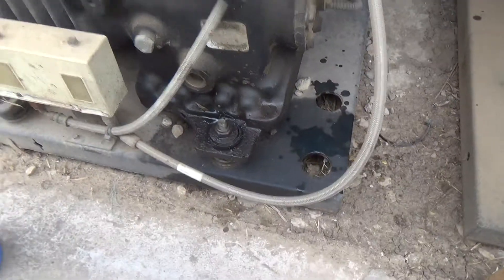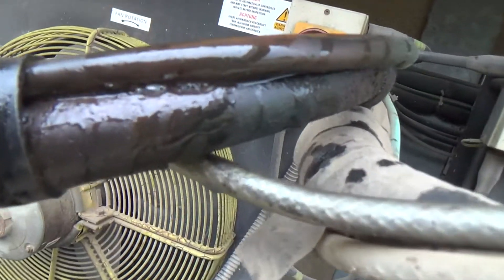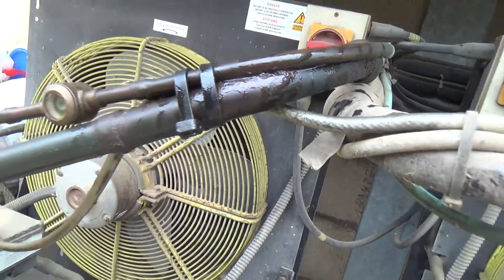The unit's cycling. It's covered in oil and it's run down the pipe from here — it's rubbed through.